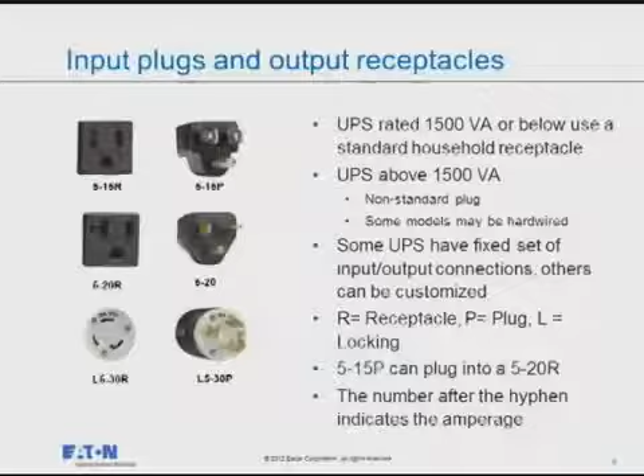If someone's saying the load requirement is 2 kVA, but I need a 5-15, well, you can't put 2 kVA on that plug, right? As your loads increase, you have to move to a 20 amp plug or a 30 amp plug. A 5-30, 120 volt 30 amp, is a 3 kVA type of application. Once I go beyond that requirement, I have to go into a 208 volt or a two-phase type of solution, similar to the stoves in our houses, which are typically about 7.2 kilowatts. If I turn on the oven and all the burners, it's about 7 kilowatts for a stove. So that's a 6-30, or a 14-30 if I have the neutral.